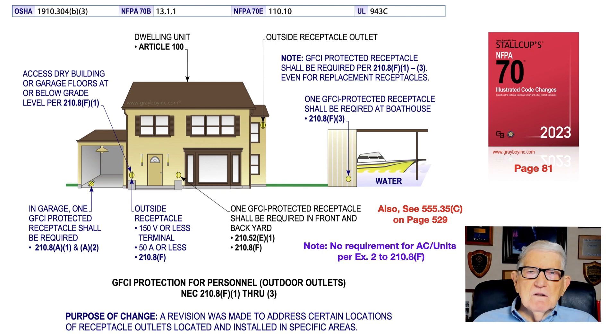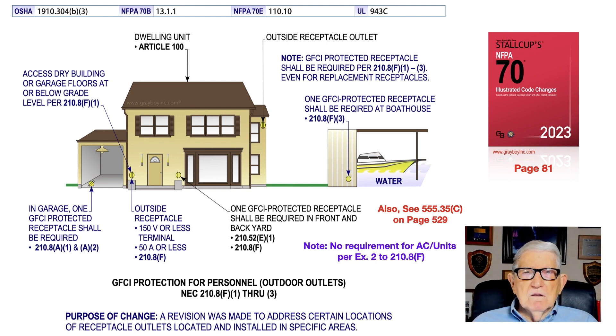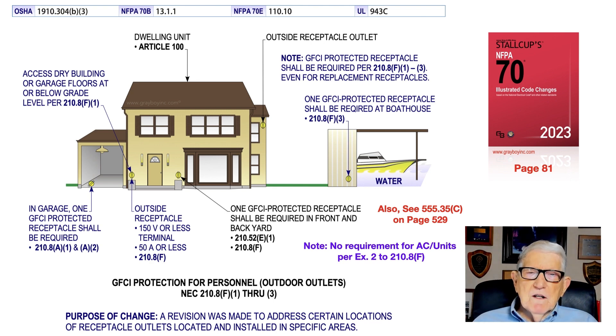The note above the boat dock area states that any outside receptacles that are replaced and not GFCI protected would need to be GFCI type receptacle outlets in accordance with 210.8 F1 through F3. Note that there is no ground fault protection required on a circuit supplying an AC air conditioner unit, as covered in exception 2 to 210.8 F.